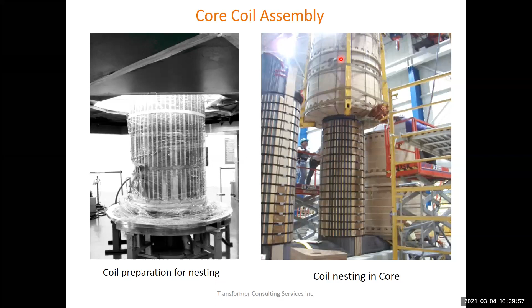Now look at it. If your factory is not climate controlled, what will happen? Those cores will absorb moisture from the environment. And when you are trying to land the coil on the core, it will be much tighter. Once you land it and put it into the drying phase, it will extract the moisture. When it extracts the moisture, the coil will become loose against the core, against the cylinder. If it becomes loose against the cylinder, and the transformer experiences repetitive faults or other things, the transformer will fail.